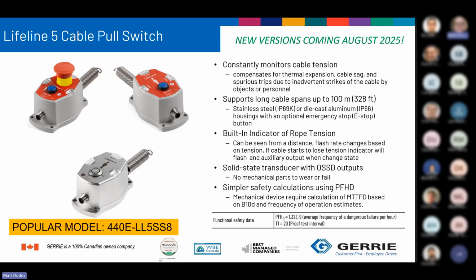I have been party to some recalls on these products due to they forgot to grease the internal contacts and they did change state. So with this type of product, you're not going to have those kind of failures. And it's simpler safety calculations using probability of dangerous failure per hour calculation. So mechanical devices require the calculation of a mean time to failure to danger based on B10D and frequency of operation estimate. So again, a lot of calculations. B10D is, they test a bunch of these switches, and when 10% of the lot fails, that is the B10D value. So with this, again, it is easier to do your calculations. Same applies for SensaGuard and the MZ switch as well.